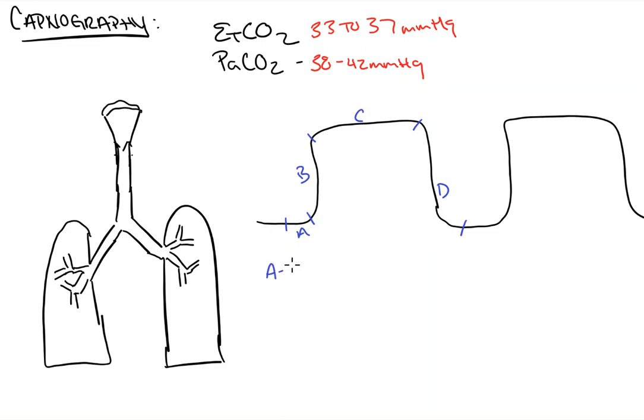So part A represents the start of exhalation. When we exhale, the first sample of air that becomes mobilized and that is seen by the CO2 sensor is the air closest to the sensor, which translates to the first air the sensor sees will be air that's here in the larynx and the rest of the trachea and the main stem bronchi and all parts of the airway that we know as dead space. Dead space are portions of the lung that do not undergo gas exchange. There's no alveoli there. But I encourage you to take a look at the VQ video for further exploration of the concept. Room air at baseline only contains trace amounts of CO2, while exhaled air can contain four to five percent CO2.